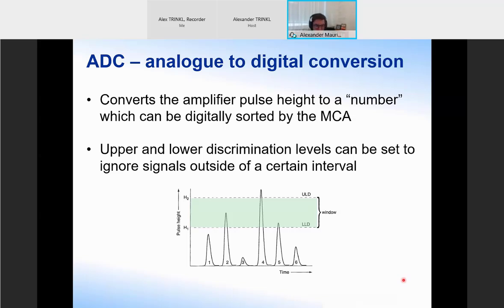This is also where you can put limits on which pulses you are actually interested in. Pulses of a certain height you might want to keep, and those outside this range you might want to reject. Here's a typical example of a rejection where I'm only interested in the voltage pulses from the amplifier with heights between H1 and H2, and all the other ones, which are either too big or too small, I reject and don't process further. This can be a typical way of reducing the noise in your spectrum by discriminating away low energy noise, for example.